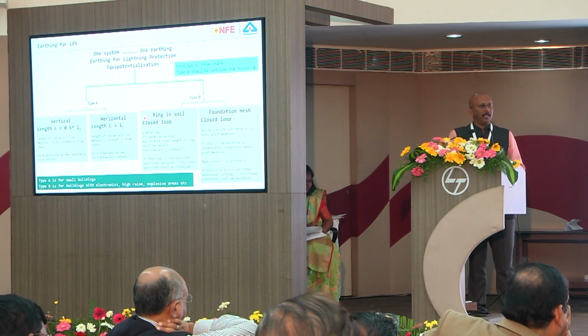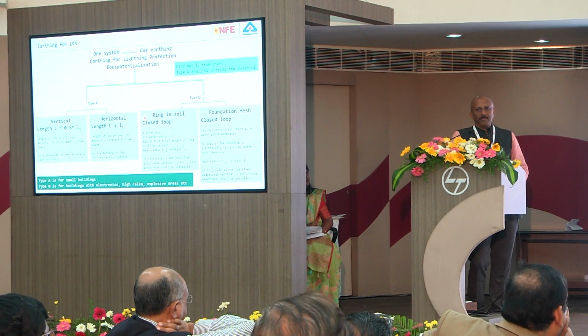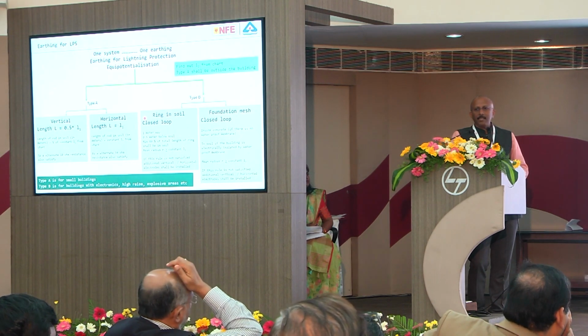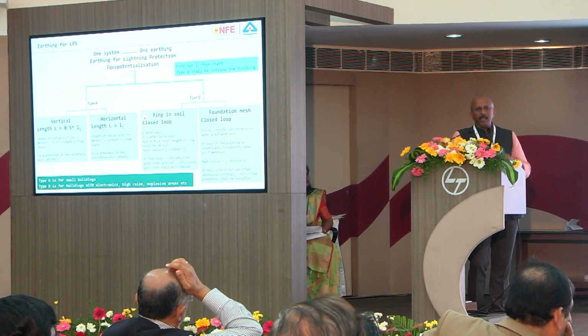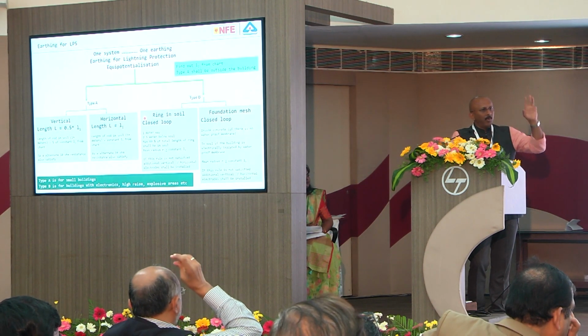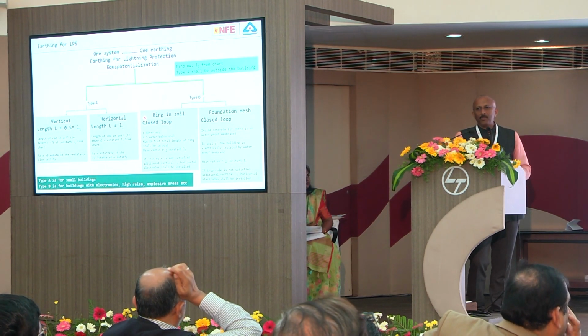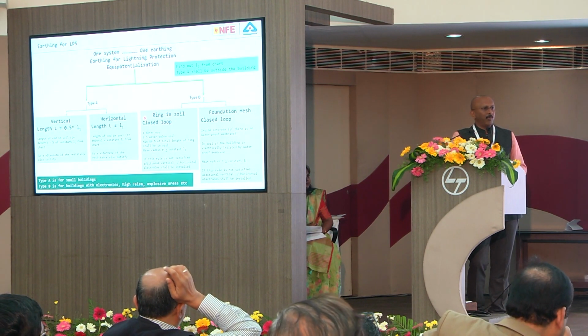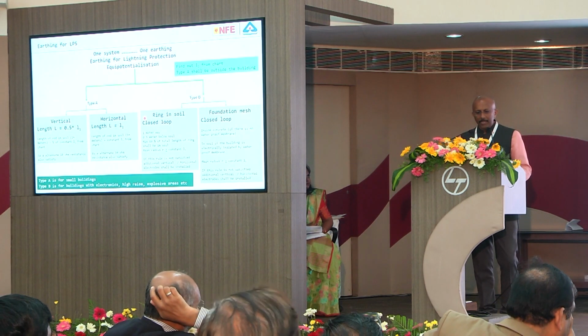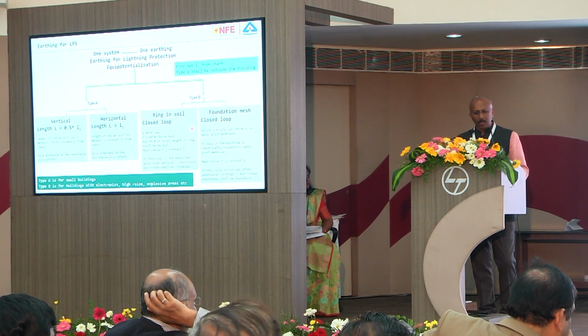Even though this is written in the standard, for example, most of the data centers in Bombay, there are so many data centers. Most of the data centers have 20 earth pits, 40, 50 earth pits, so many down conductors. But unfortunately, 10 numbers are routed through one shaft. Then these 10 numbers have 10 different earth pits. So this is actually a waste of money. It is not going to work. Even if you avoid it, the result will be the same. Basically, for places where you have electronics, you are supposed to have a foundation mesh or ring earth.